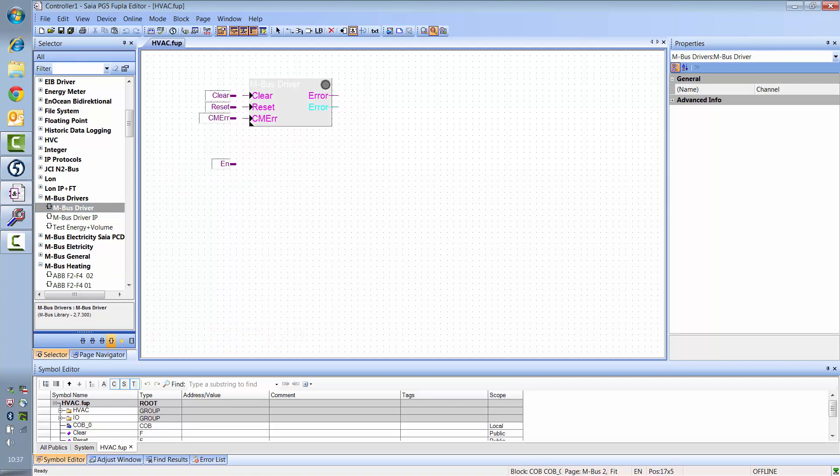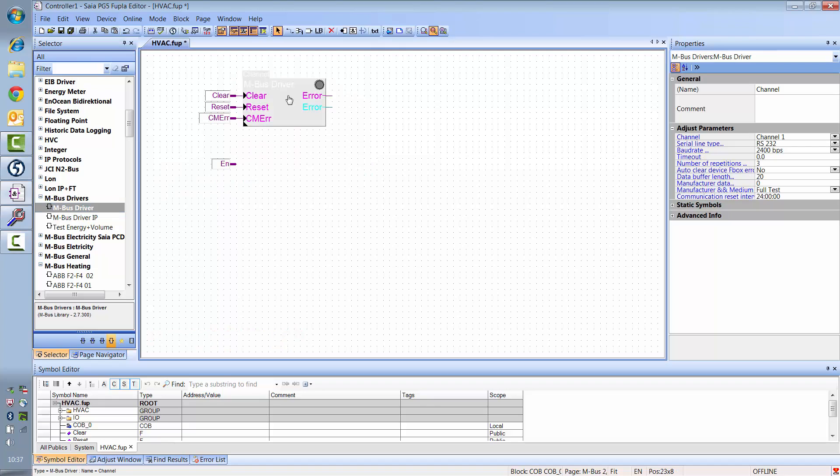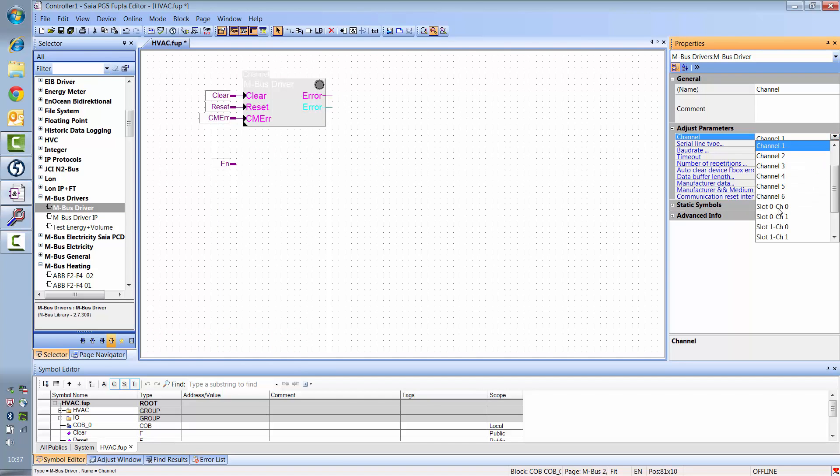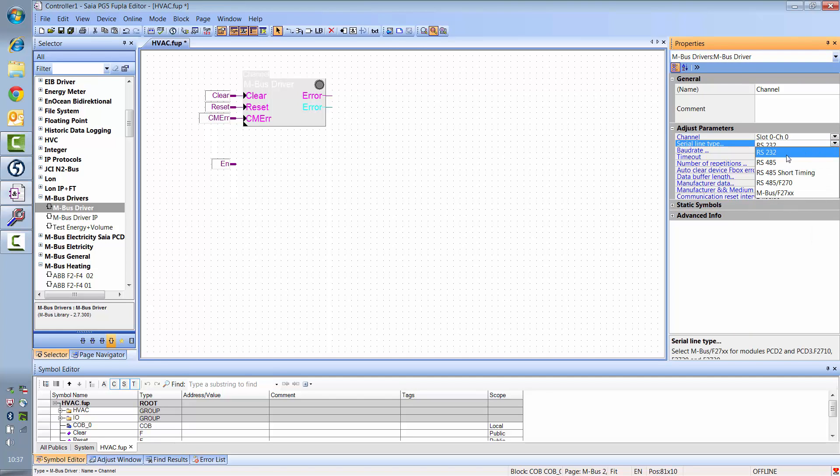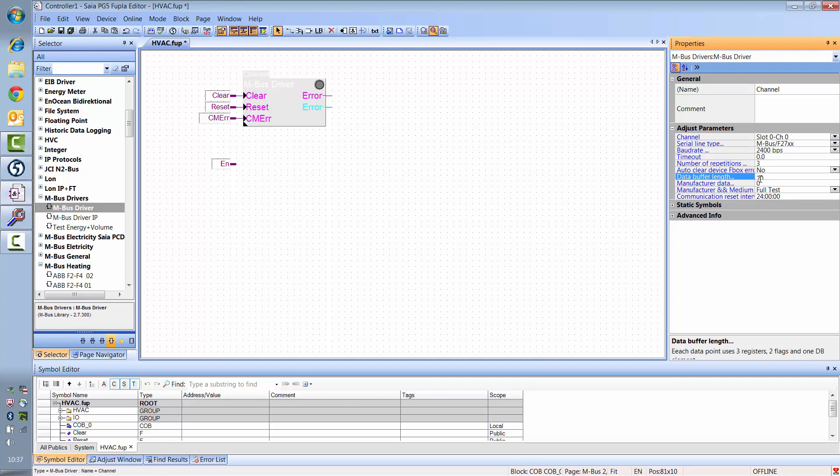First, position the M-Bus driver and set the channel through which the card communicates. In our setup, the card is in slot 0 and we use channel 0 on the card. The line type is M-Bus F27XX. We also set the data buffer length to 50, as our meter delivers a very large amount of data.